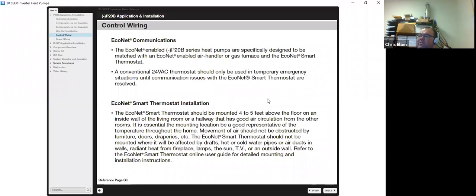EcoNet smart thermostat installation. It should always be mounted 4 to 5 feet above the floor, on the inside wall of the living room or hallway that has good circulation from other rooms. It is essential that the mounting location be a good representative of the temperature throughout the home. Movement of the air should not be obstructed by doors, furniture, draperies. Also should not be affected by drafts, hot or cold, TVs, fireplaces, lamps, direct sun that will skew your readings.